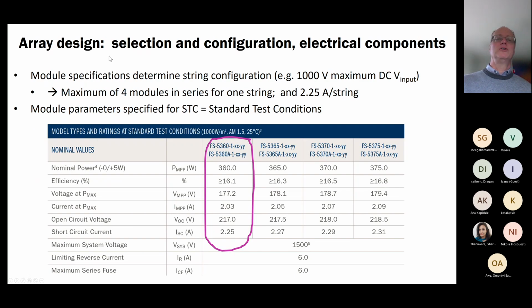And so when you're considering the modules with regard to the inverter, I just mentioned that there's a maximum string voltage or input voltage, and that's 1000 volts for these particular inverters. So then you can go down to your module parameters and look at the maximum voltage, which is going to be the voltage at open circuit. In this case, it's about 217 volts. And so just by doing a little bit of math, you can tell that 217 times 4 modules in series is still less than 1,000 volts. But if you add a fifth one, then you'll exceed that 1,000 volt maximum. So you can have 4 modules in series for one string, and your maximum current for that string would be the current of a single module, which is 2.25 amps.